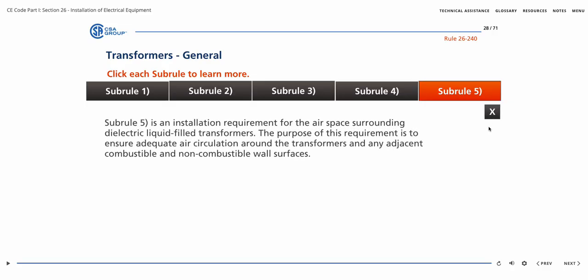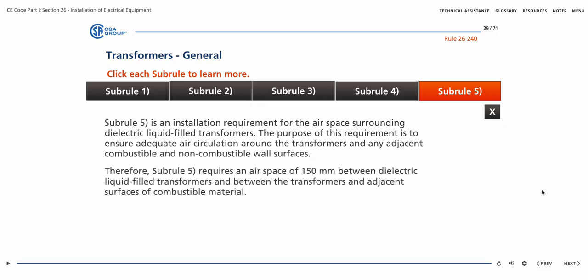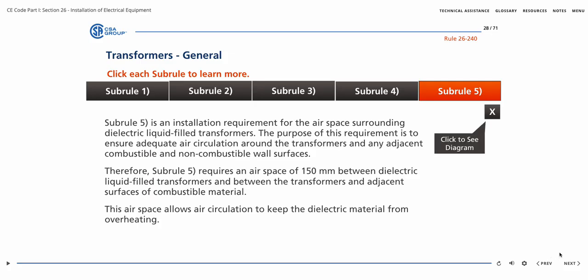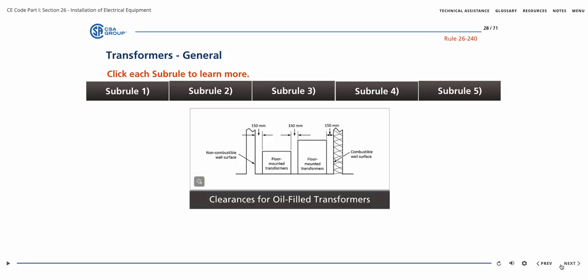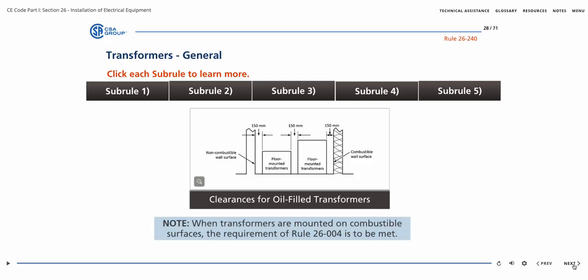Subrule 5 is an installation requirement for the airspace surrounding dielectric liquid-filled transformers. The purpose of this requirement is to ensure adequate air circulation around the transformer and any adjacent combustible and non-combustible wall surfaces. Therefore, Subrule 5 requires an airspace of 150 millimeters between dielectric liquid-filled transformers and between the transformers and adjacent surfaces of combustible material. This airspace allows air circulation to keep the dielectric material from overheating. See the diagram on the screen for clearances around oil-filled transformers. Note, when transformers are mounted on combustible surfaces, the requirement of Rule 26-004 is to be met.